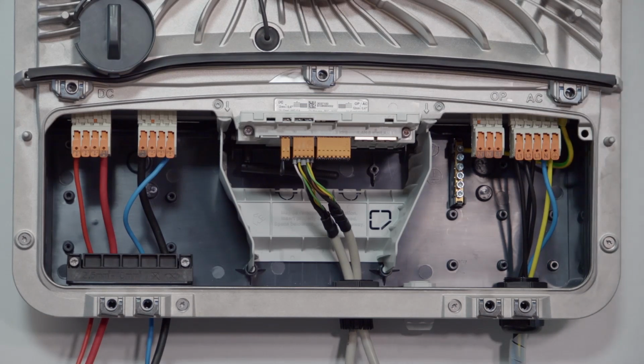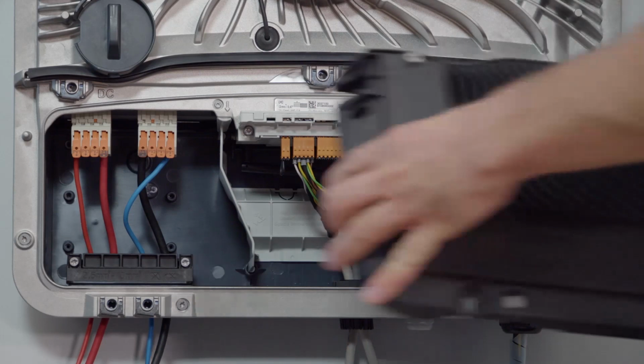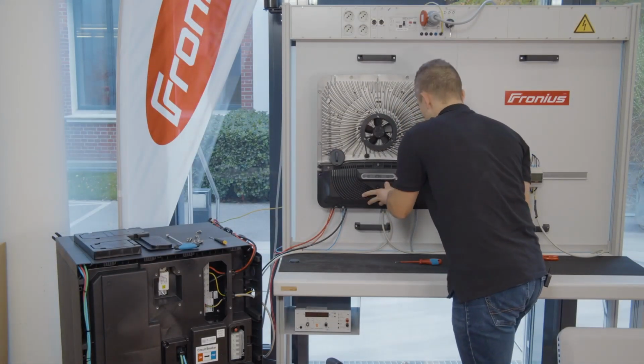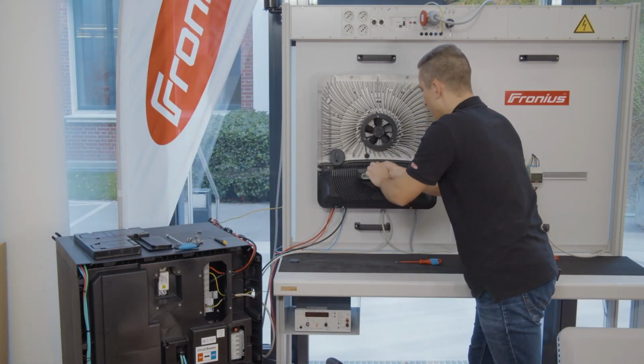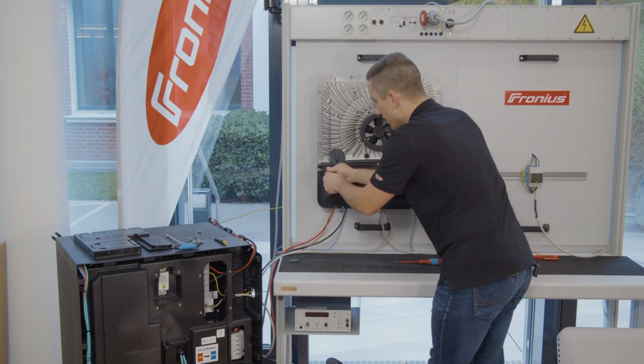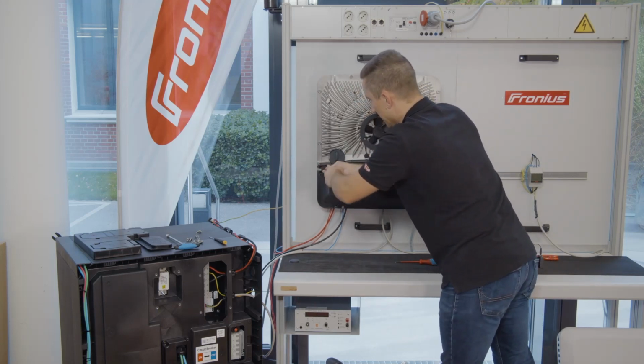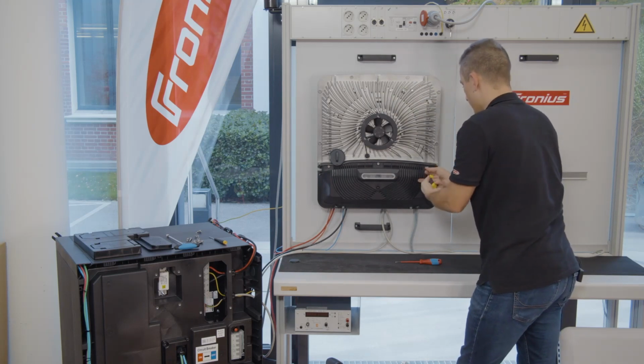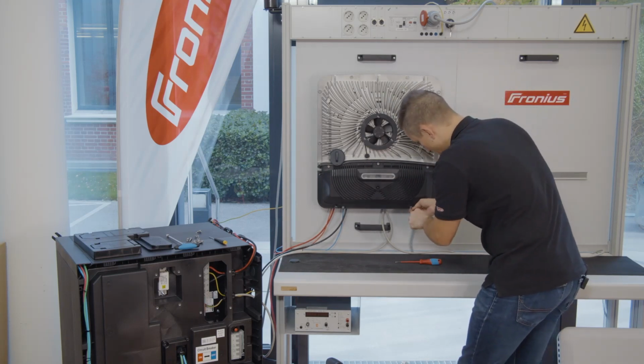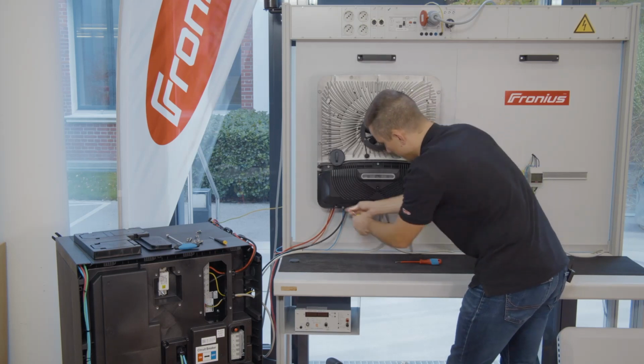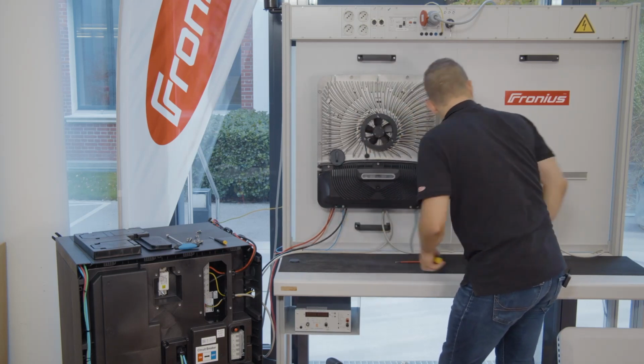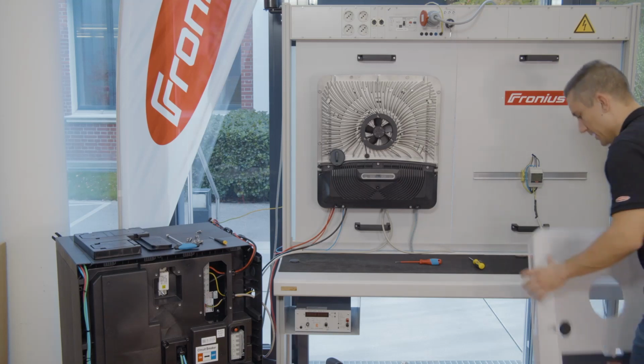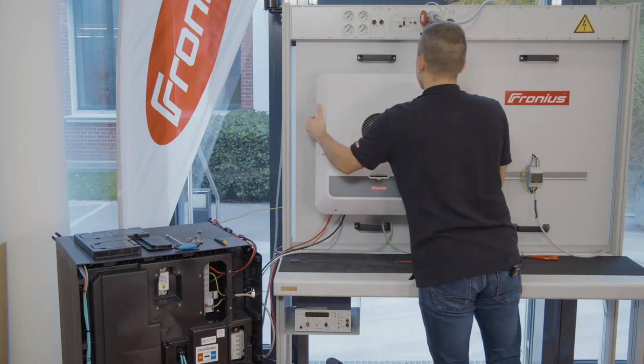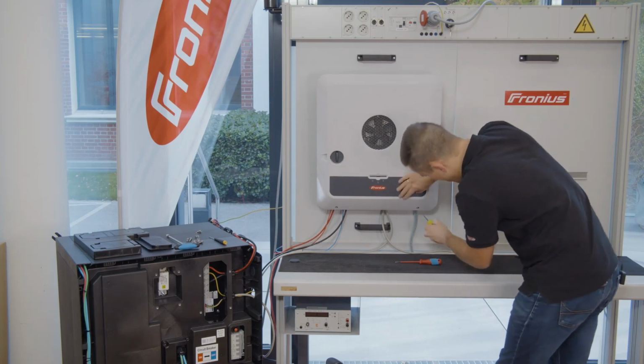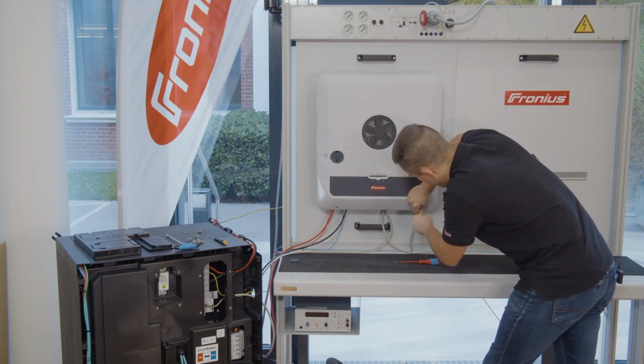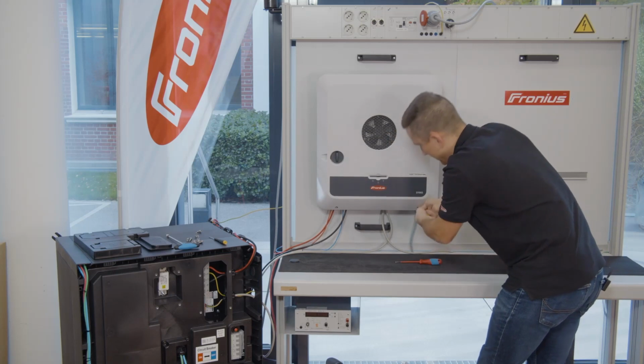Therefore we are finished with the GEN24 Plus installation, and for that we can install the data communication cover back on again. For that we again need our Torx 20 screwdriver, and with our fast locking screws we can close down the cover again to make sure that the connection area is properly closed. And last but not least, we can place back the cover of the GEN24 Plus onto the device, and again with the fast locking screws we can make sure that the cover is set in place again.